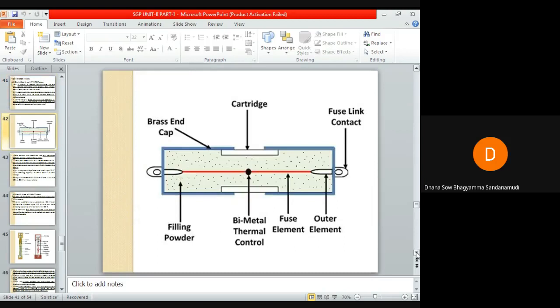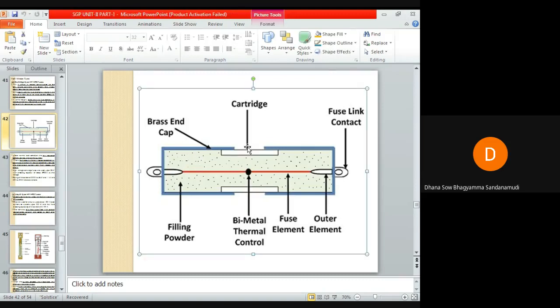The construction of this cartridge type HRC fuse is almost similar to the cartridge type HRC fuse of low voltage. The low voltage and high voltage cartridge type HRC fuse constructions are almost similar, except that there is a special feature incorporated in this device, which is not shown here. I have shown the same image here.